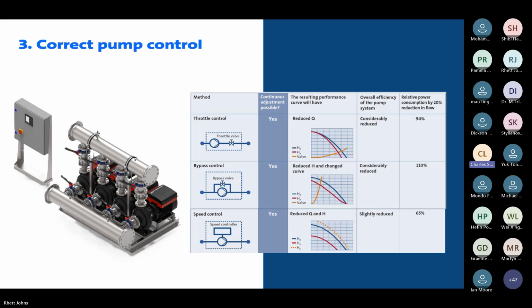So we know as we start to close that valve, our duty point is going to move up the curve. But obviously the pump is still running, still using all of that power that we don't need. We've actually used the valve to change the pump performance there. We haven't changed anything in the pump itself.